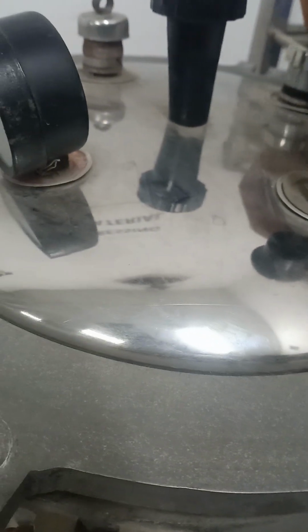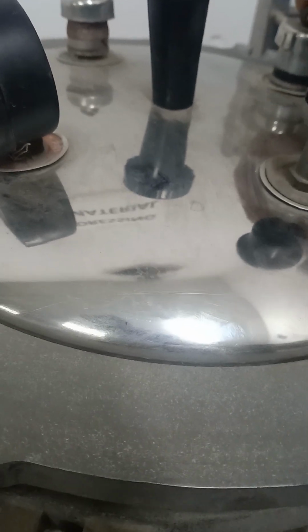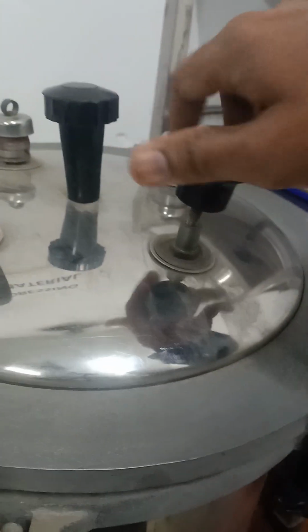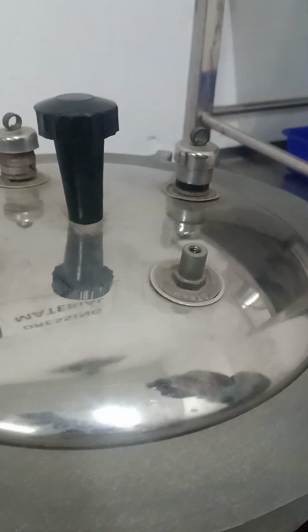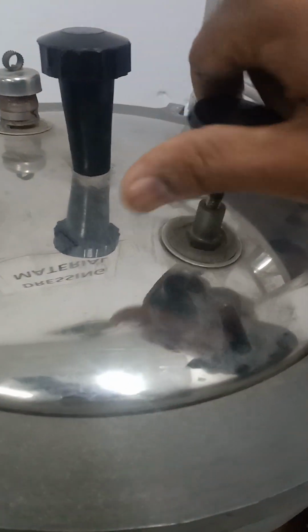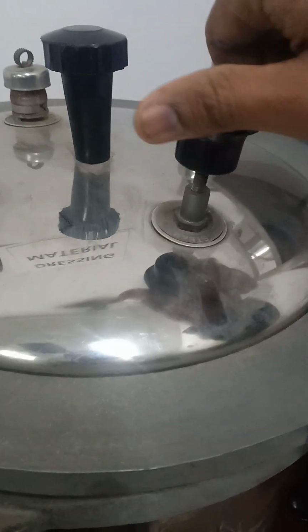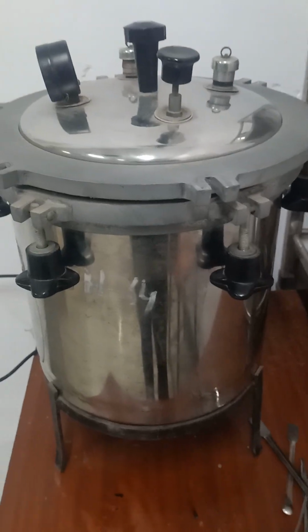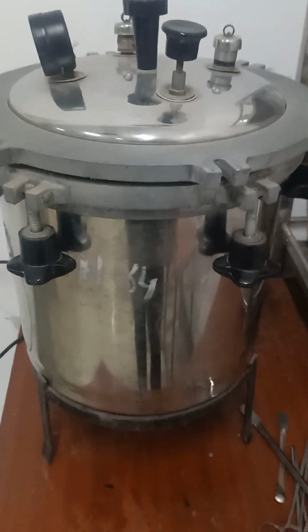There is a steam valve. After 15 or 20 minutes the steam will release from this safety valve, and if you want to remove all the steam completely, here is a steam reliever, you can see easily. So this is the basic principle and basic working of the autoclave.